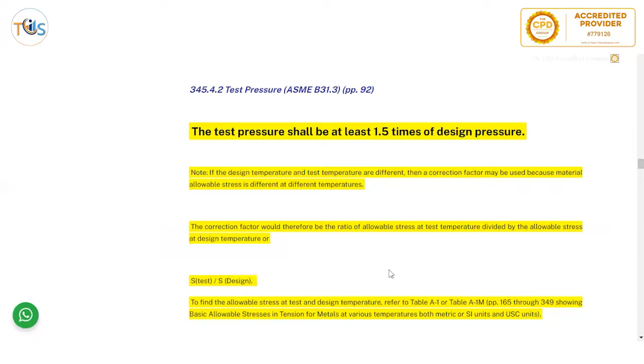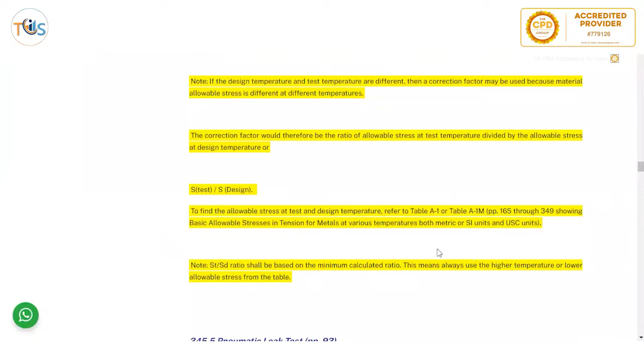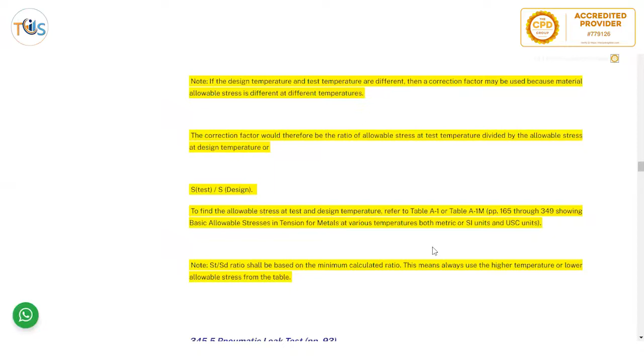The correction factor would therefore be the ratio of allowable stress at test temperature divided by allowable stress at design temperature, or S test divided by S design. Now, find the allowable stress. Again, you go to table A1 or A1M. So this is like a 150 page or 200 page document just for this table, because it covers all the materials and all the temperature range for each material. So you go there and find the allowable stress in tension for metals at various temperatures. This is both metric and US units.